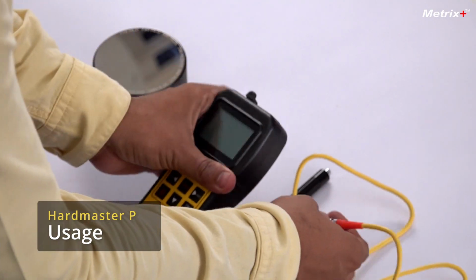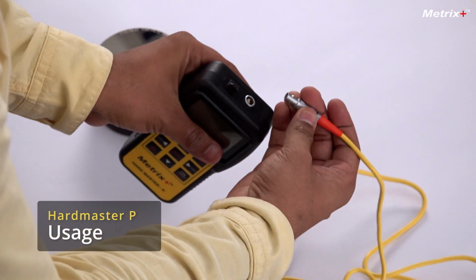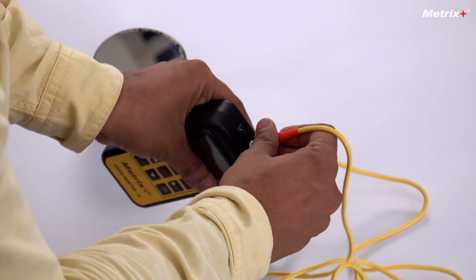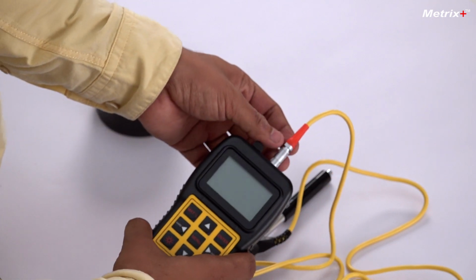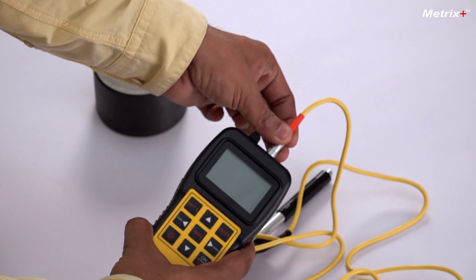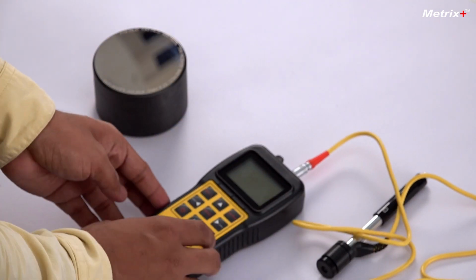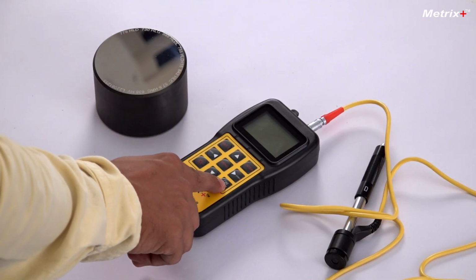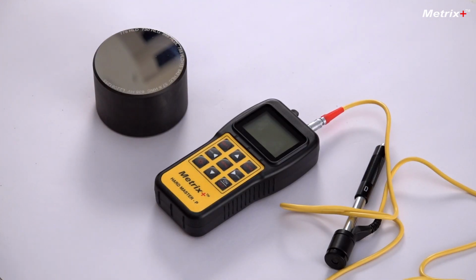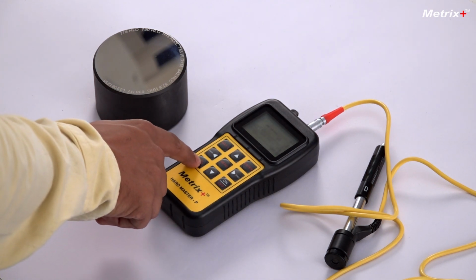Let's see how to operate this meter to measure the hardness. First, we'll connect the probe. So this is where the connection should be made. Once it's connected, make sure that it is tight and it is not loose. After that, we switch on using this button. So we switch it on. This is the backlight button to see more clearly.